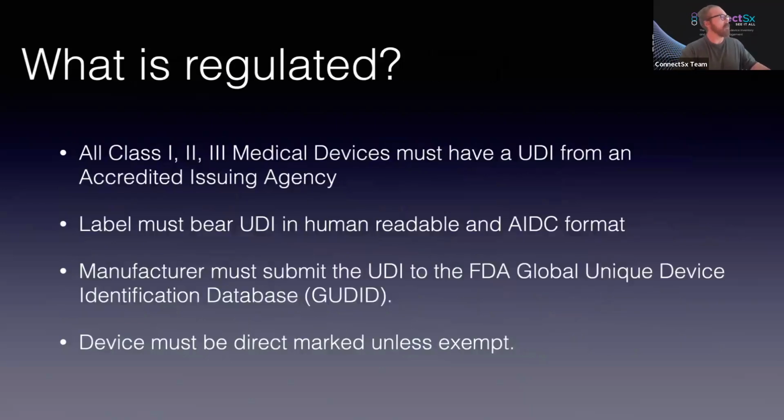So what exactly is regulated? And I tried to simplify this so that we didn't actually go into all of the language. There's a lot written about the UDI final rule, even within what the FDA published. But essentially, all medical devices must now have a UDI from an accredited issuing agency. And we'll talk about who those are.